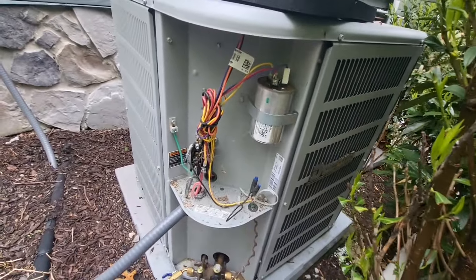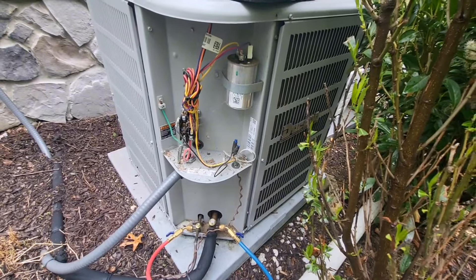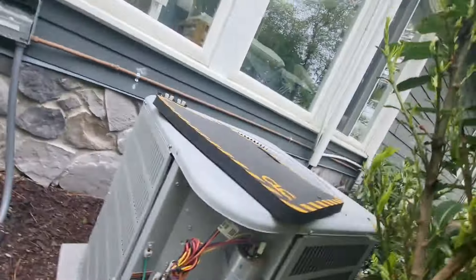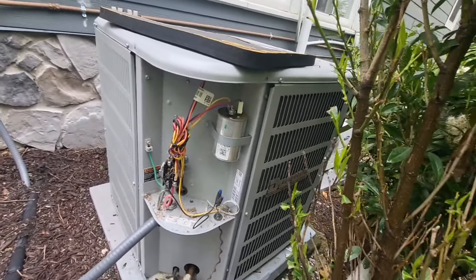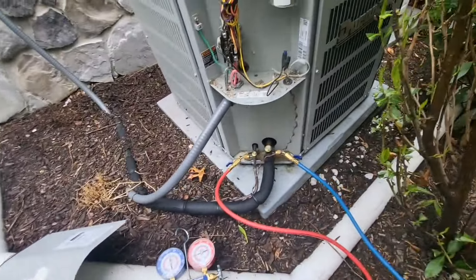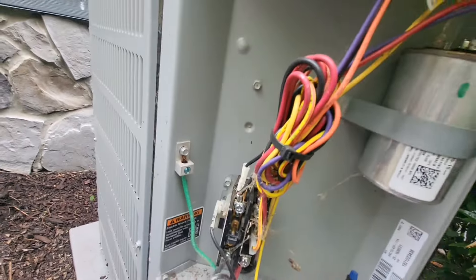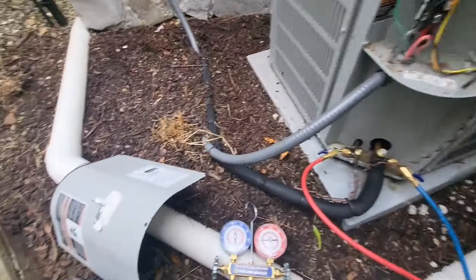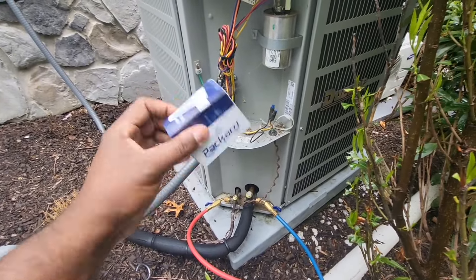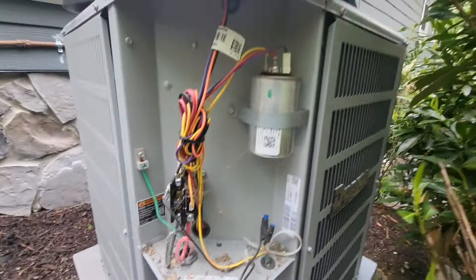I'm out here today for no AC — this contactor shorted out. I'm finding the same faults as previous videos. There's an AC-only air handler in the attic and the fuse was tripped upstairs. I know for sure we ran new wiring when we put this unit in, but the fuse only stops tripping when I put the wires on the new contactor coil.